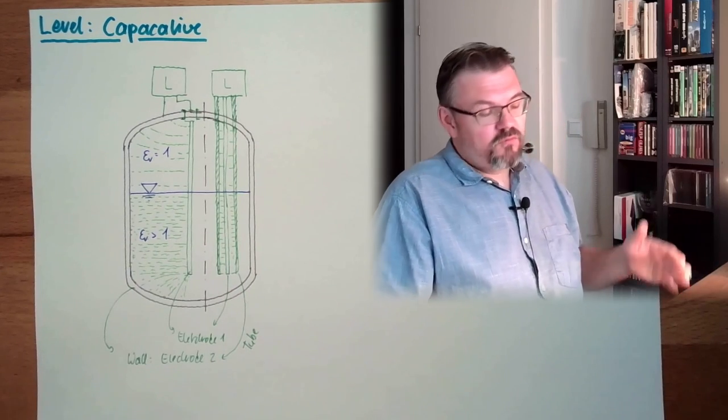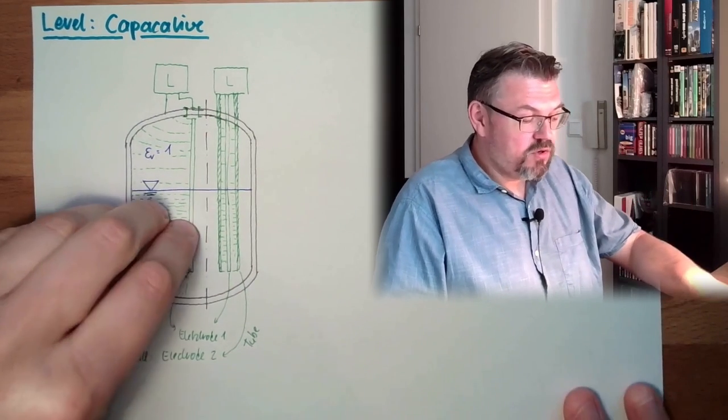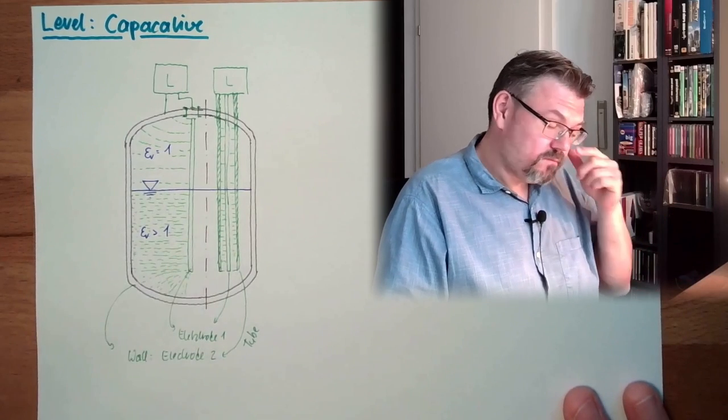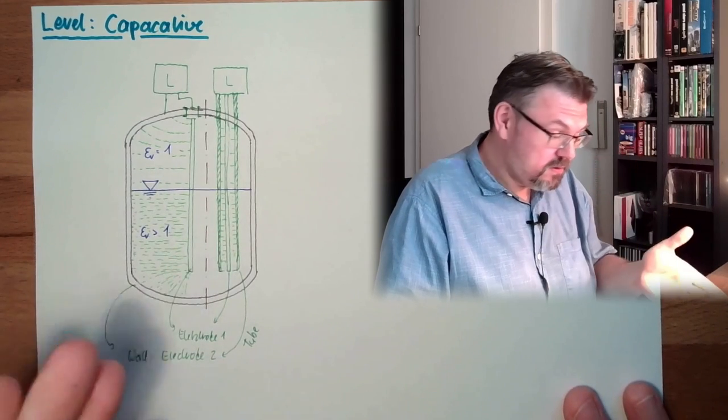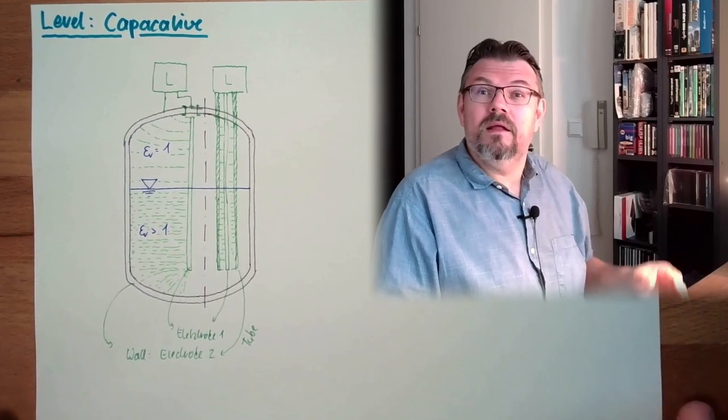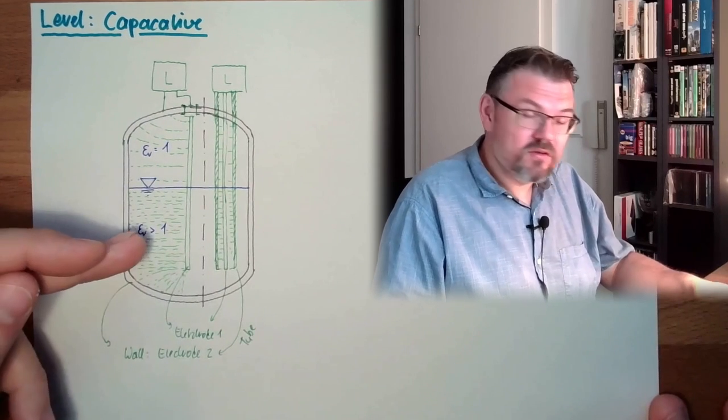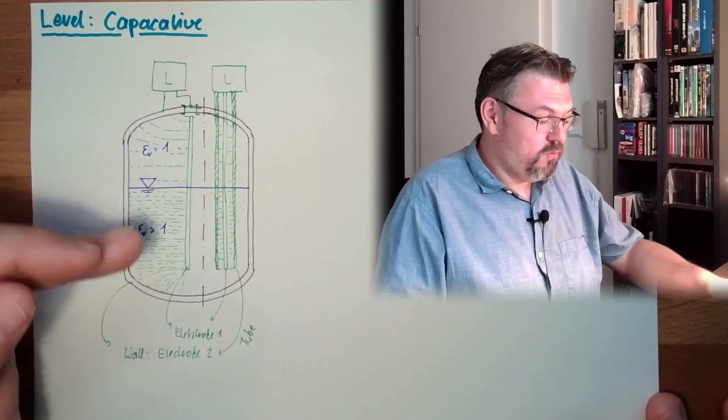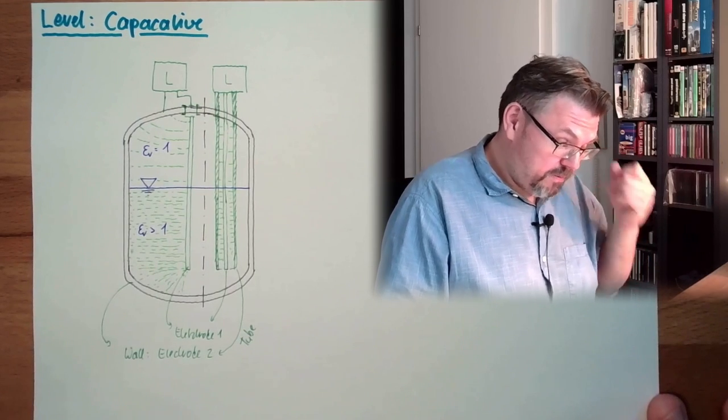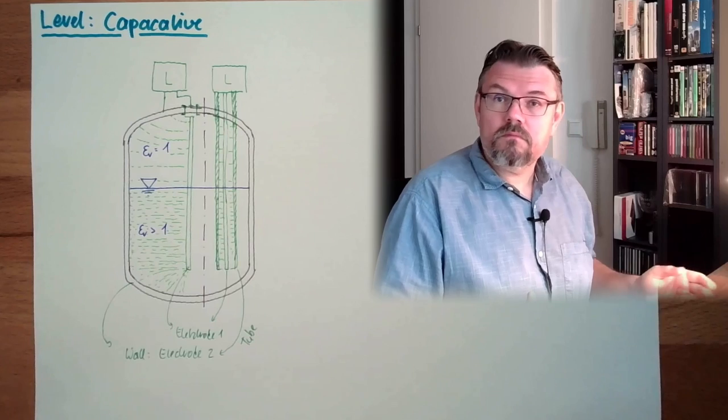Can be used for bulk materials. This can be used for bulk materials. This is not that good for bulk materials. Can be used for liquids, of course. The only important thing is that this is not conductive and we have a difference between the epsilon r's. That's it.